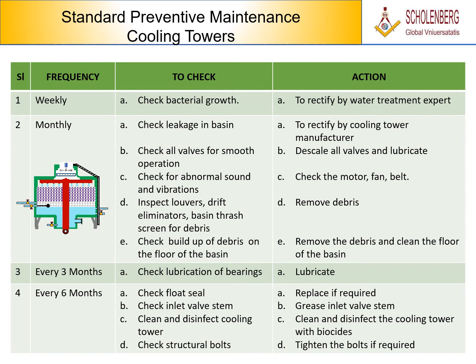C. Check for abnormal sound and vibrations. Action. Check the motor, fan, belt. D. Inspect louvers, drift eliminators, basin trash screen for debris. Action. Remove debris. E. Check buildup of debris on the floor of the basin. Action. Remove the debris and clean the floor of the basin. 3. Frequency. Every 3 months. To check. A. Check lubrication of bearings. Action. Lubricate.